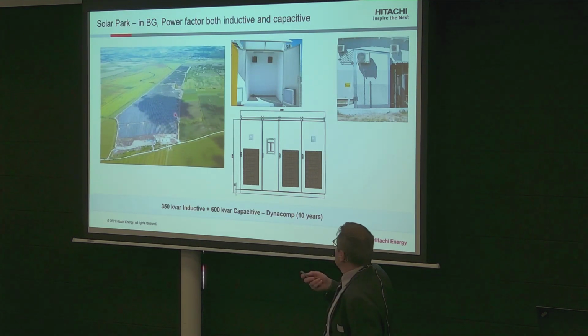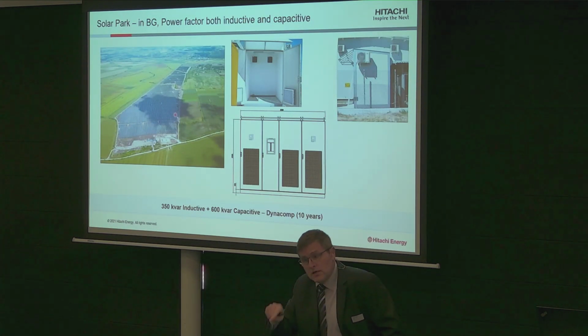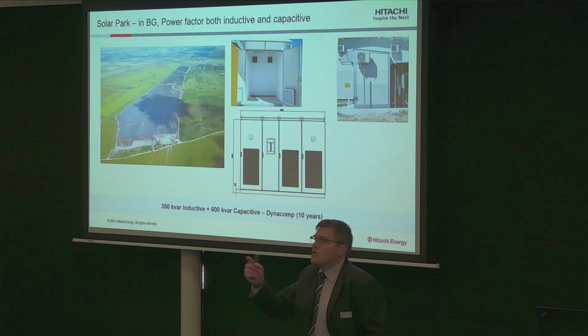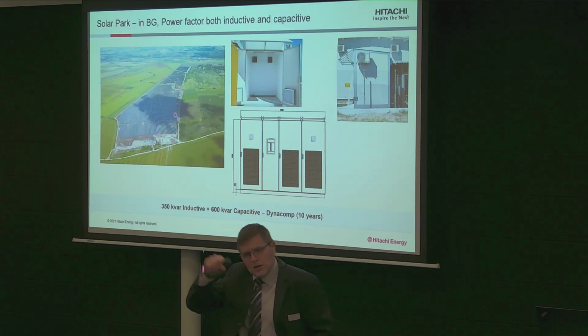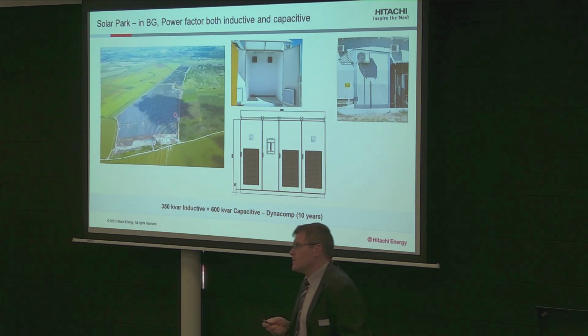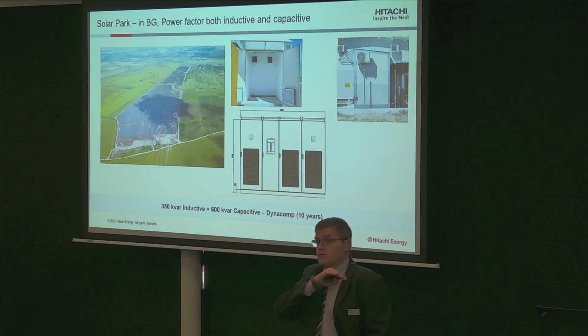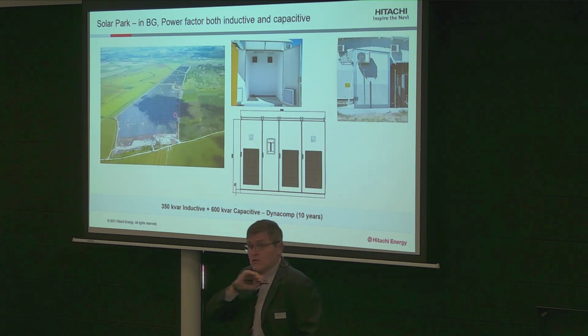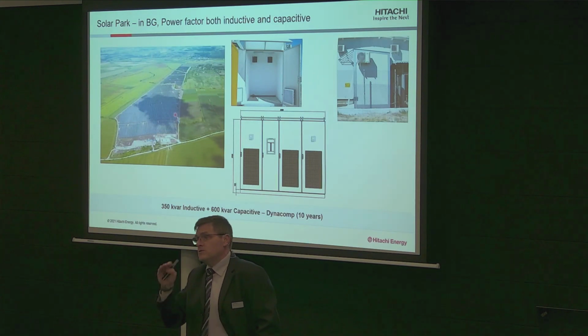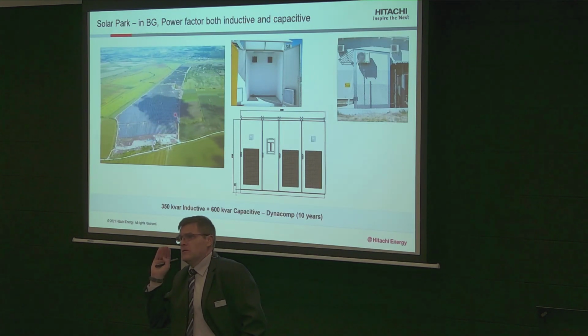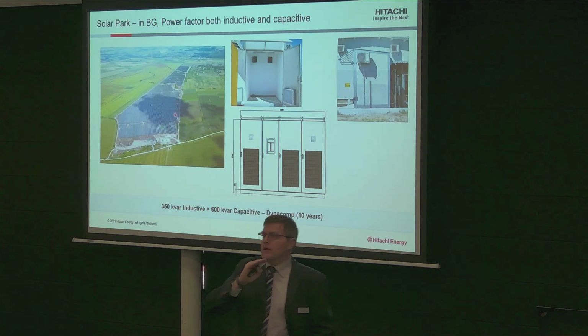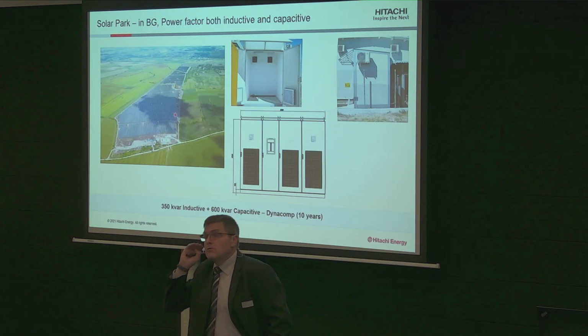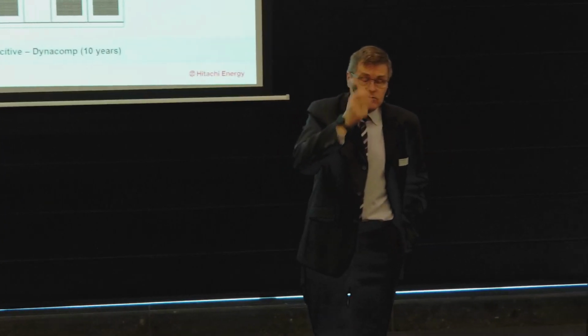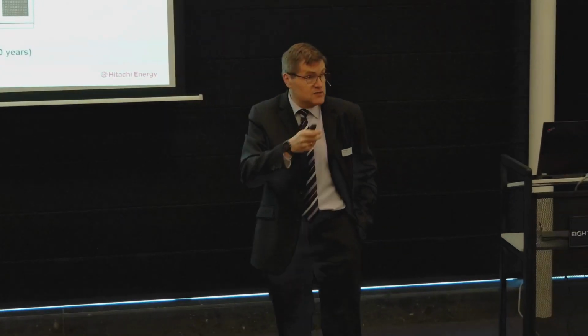So another type of application with green energy, because the rules, the grid code, impose a very high power factor. In Turkey, because the grid is totally saturated, the target power factor is 0.995. In India, we have 0.998, so we are very close to 1. So they really want to reach unity because of saturation of the grid. Okay.